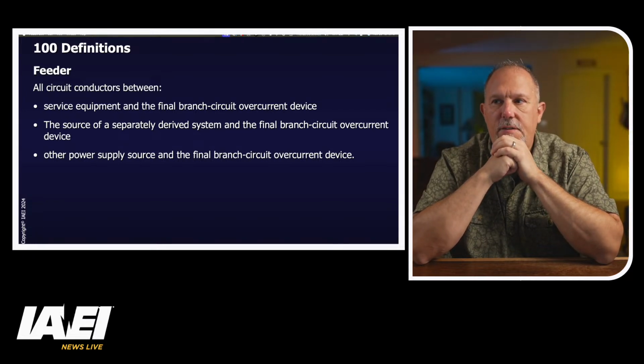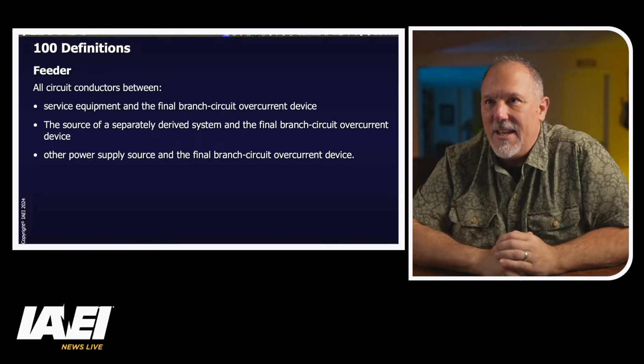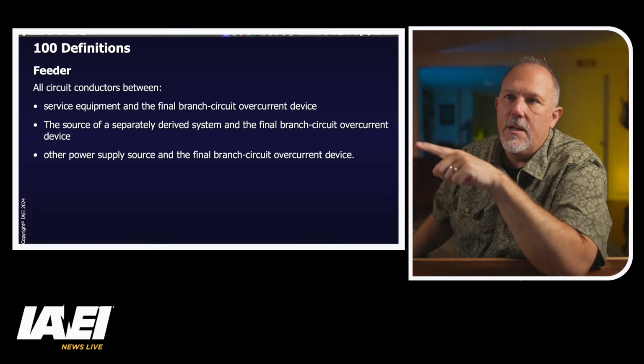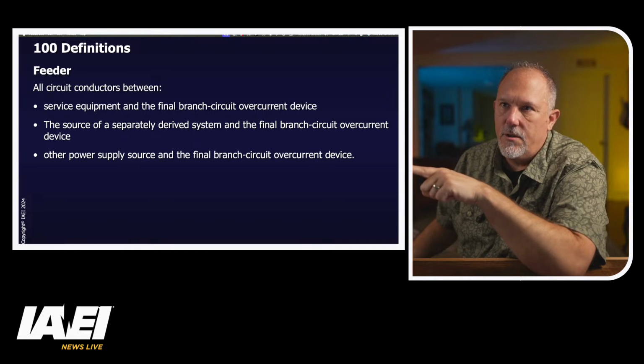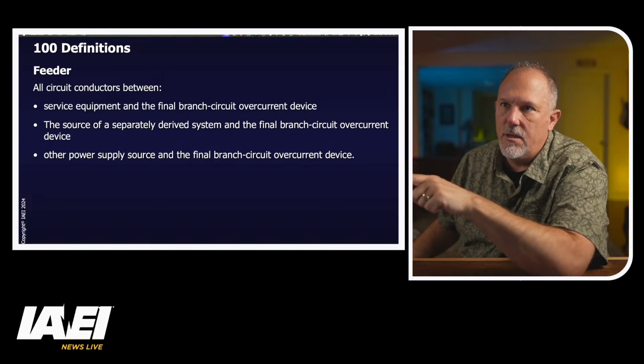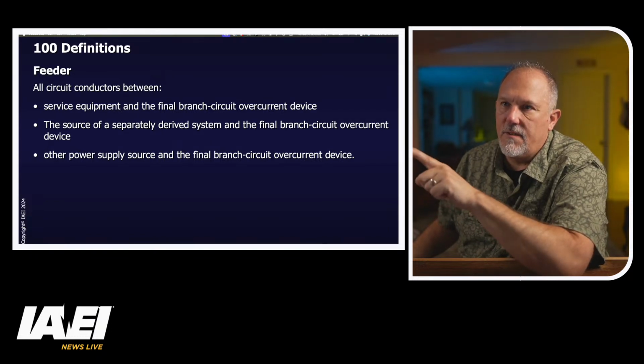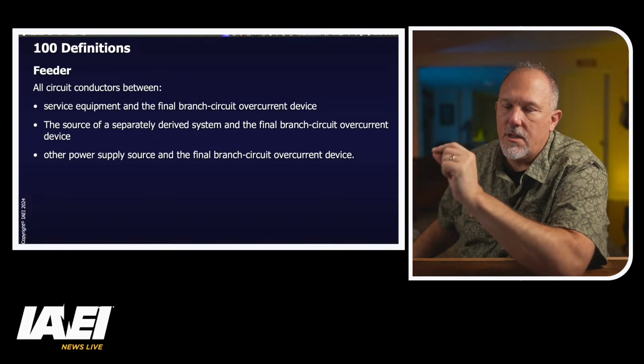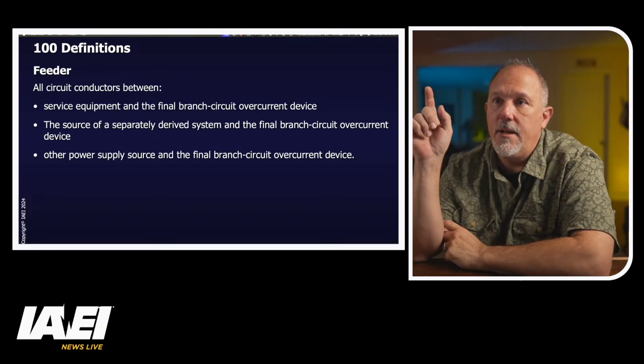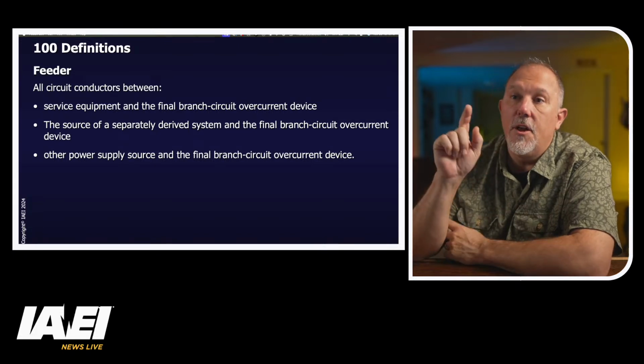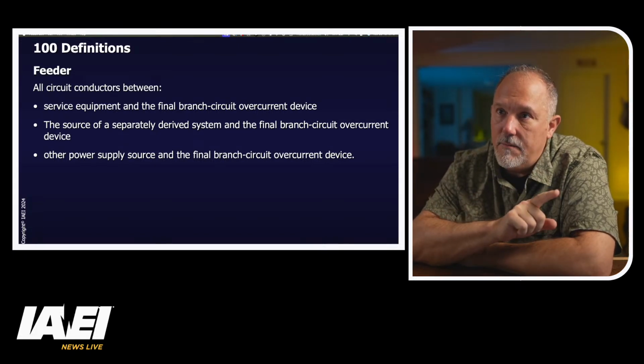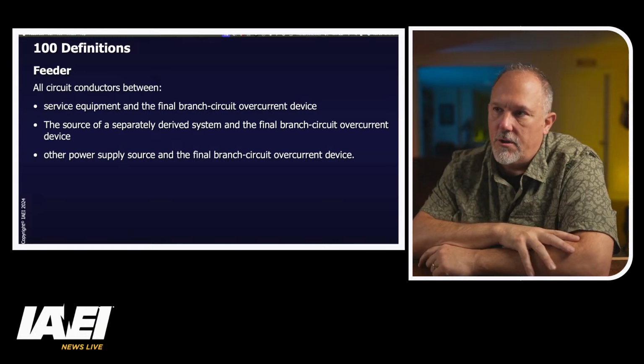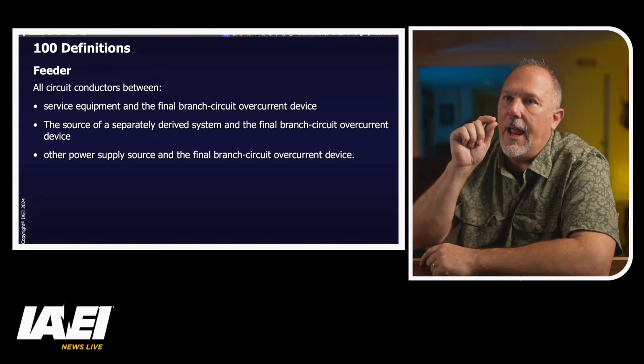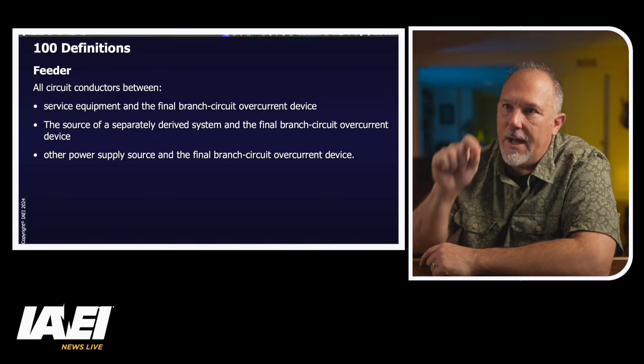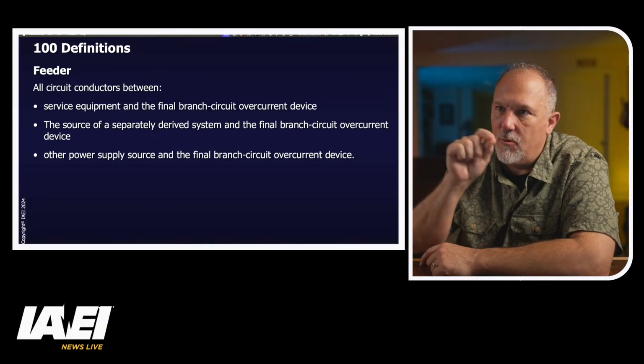The definition of a feeder is all circuit conductors between service equipment and the final branch circuit overcurrent protective device. So it's all circuit conductors between service equipment and the final branch circuit overcurrent device, the source of a separately derived system and the final branch circuit overcurrent device, and other power supply source and the final branch circuit overcurrent device.